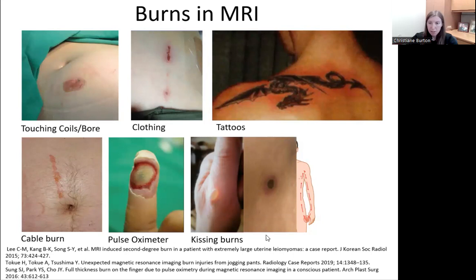Burns from cables in the MR machine touching the patient can occur. Skin contact must be avoided by padding and positioning. The wires should not be allowed to cross the patient. They should be run down the center of the MR system out between the patient's legs, not alongside of the system close to the RF coil. If more than one wire is exiting, try to leave a little space between them to prevent capacitive coupling.